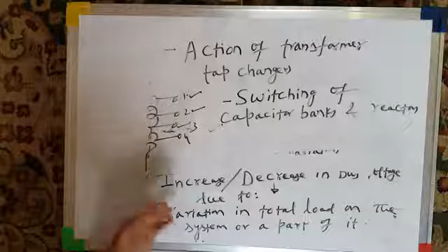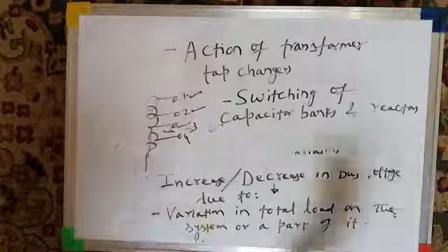So this is the first type of voltage and current variation, that is voltage magnitude variation. Voltage magnitude variation means increase or decrease in the bus voltage, which may be because of three causes. Number one, variation in total load on the system or part of it. Number two, action of transformer tap changers. And number three, switching of capacitor banks. So I hope this is clear.